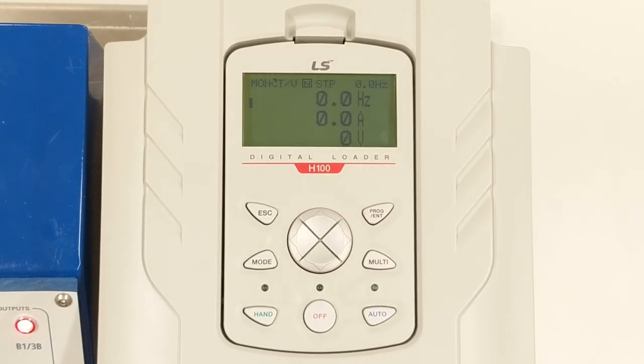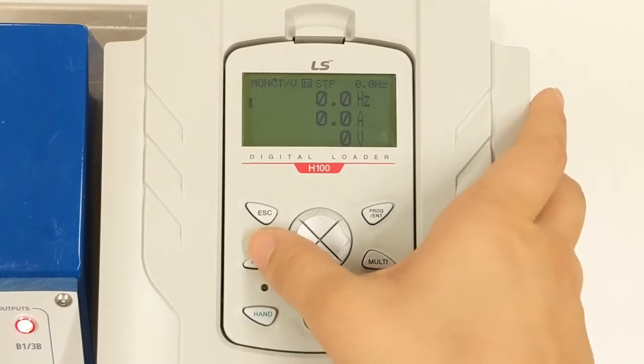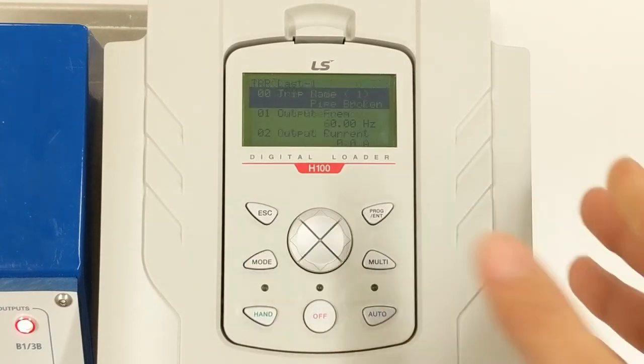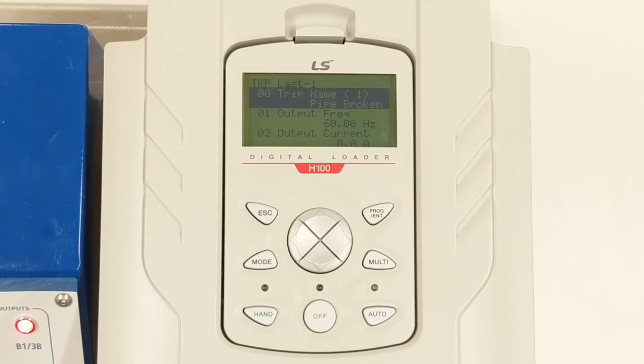There are a couple of other keypad modes you may find useful on the H100. Press mode 2 times to go past the parameter group and into the trip group. This is designated TRP in the top left. Here you can see the 5 most recent trips that the VFD has recorded. This mode is an excellent tool for troubleshooting. If you do not have a trip mode, this simply means that the VFD has never tripped out or that all previous trips have been cleared.